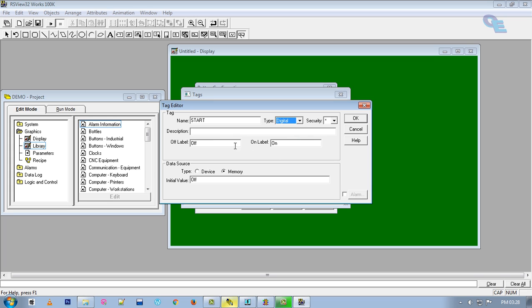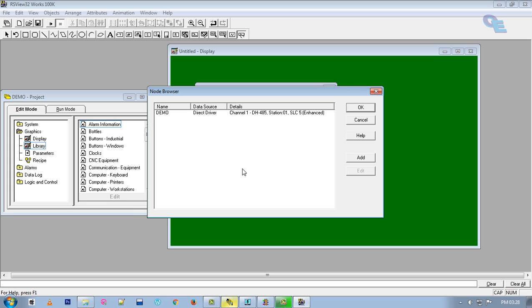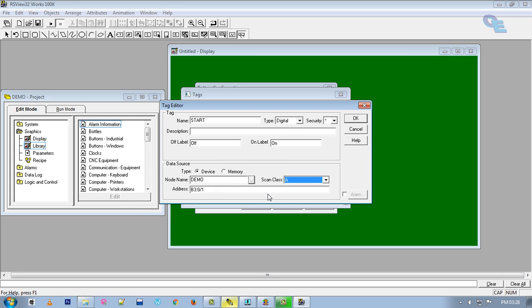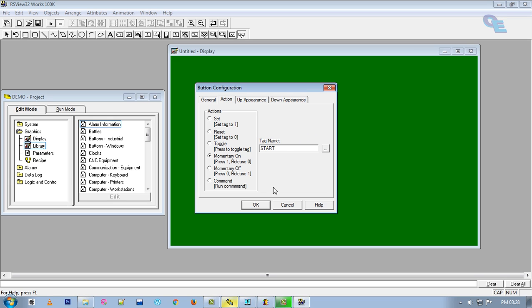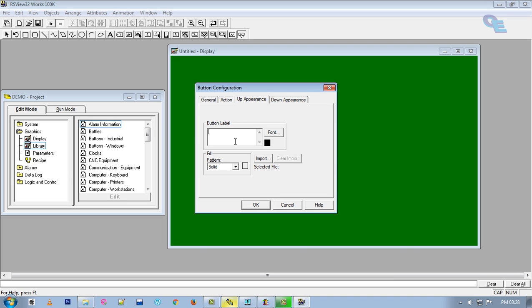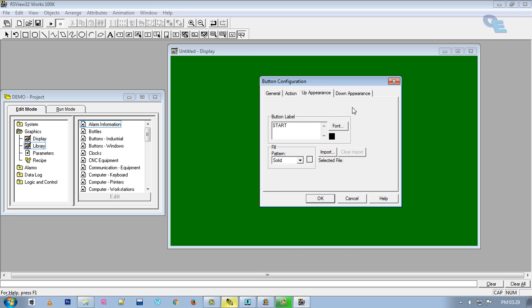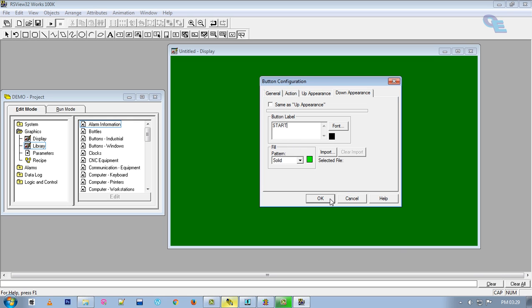Take a raised button — momentary on. When we press it is 1, when we release it is 0. Under Tags, create a new tag named 'start', type is digital, and we are using device — this is the driver we created — and B3:0/1 is our start bit. Click OK, select the start button, and when it is up the appearance should show the 'Start' title in green.